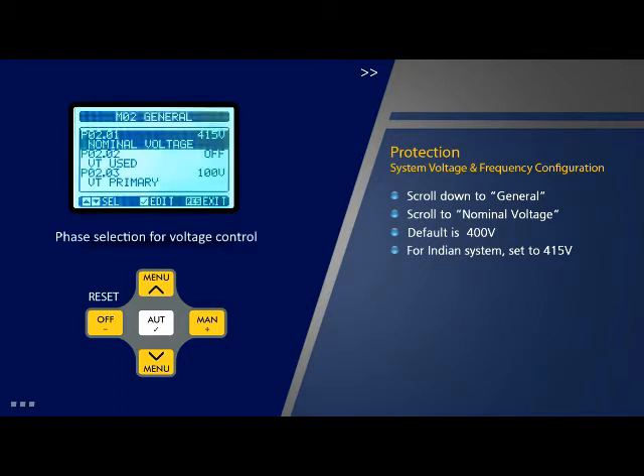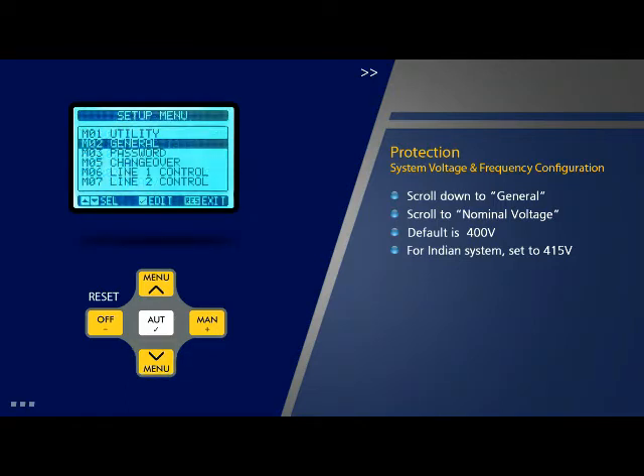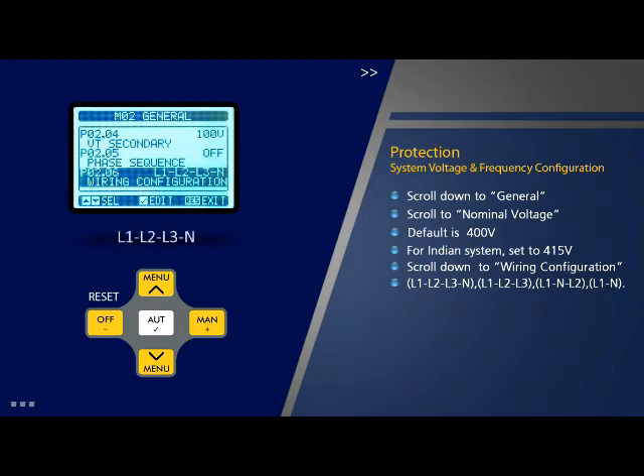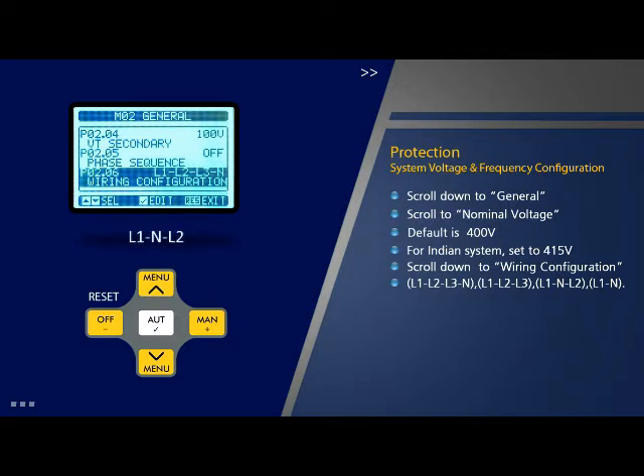Next, let us see the steps for phase selection for voltage control. Scroll down on the general page to parameter 6 which is 'Wiring Configuration' and press OK. The options available are: 3-phase 4-wire (L1 L2 L3 N), 3-phase 3-wire (L1 L2 L3), 2-phase neutral (L1N L2), and single phase (L1N). Choose the option depending on the source available at site.